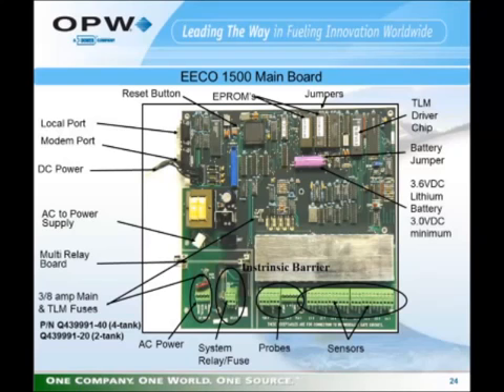On the lower right are the connectors for the probes and the sensors. Above that, you'll see the intrinsic barrier. What's not shown in this illustration is that when normally installed in the case of the EECO 1500, there is a metal cover that goes around the intrinsic section to isolate it from any high voltage that it might come in contact with.